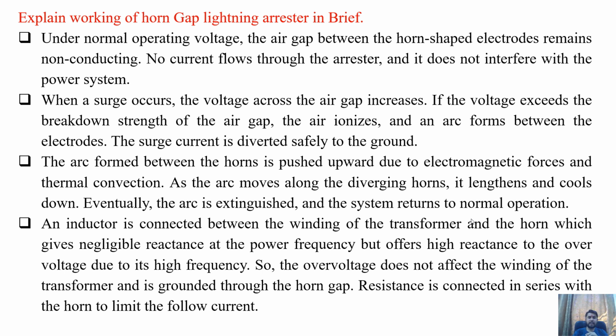An inductor is connected between the winding of the transformer and the horn, which gives negligible reactance at the power frequency but offers high reactance to the overvoltage due to its high frequency. So the overvoltage does not affect the winding of the transformer and is grounded through the horn gap. Resistance is also connected in series with the horn to limit the follow current. So this is how horn gap lightning arrestor works.